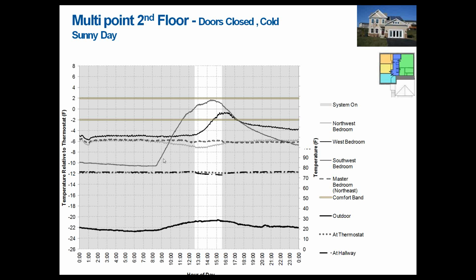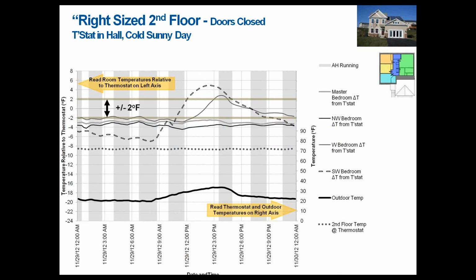And so then, as a reference point, we also looked at a case with a right-sized system supplying air to every room to see if that worked. We've looked at these simplified cases, and sometimes it does work, sometimes it doesn't, and we want to see now the impact of a traditional system. So this is the second floor, doors closed, and we see this similar problem where on a sunny day we have overheating in those sun-tempered bedrooms that don't have a thermostat in them, and they're not thermally connected to the rest of the house very well because the doors are closed. And during this period, the system did not run at all because the thermostat was satisfied, but we didn't have mixing through this period.